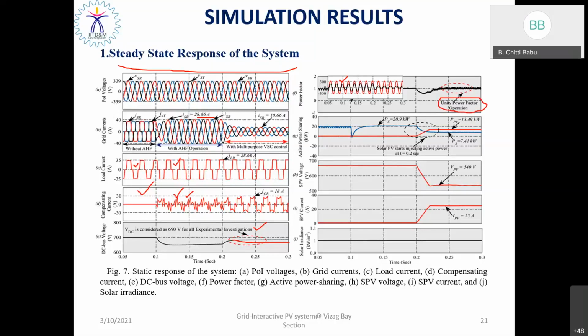And you can see when there is a sudden decrement in current from 28.66 ampere to 20.66 ampere, there is a drastic change in the active power as well, as the PV is also contributing a certain amount of power, say 13.5 kilowatts at 0.2 seconds, so that it also contributes to perfect energy sharing. So due to this active power sharing capability, it also ensures an excellent energy management system between the solar PV and the utility grid. The corresponding PV voltage and PV current are available here.